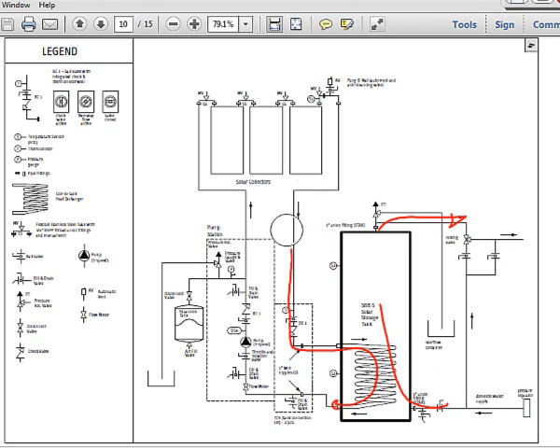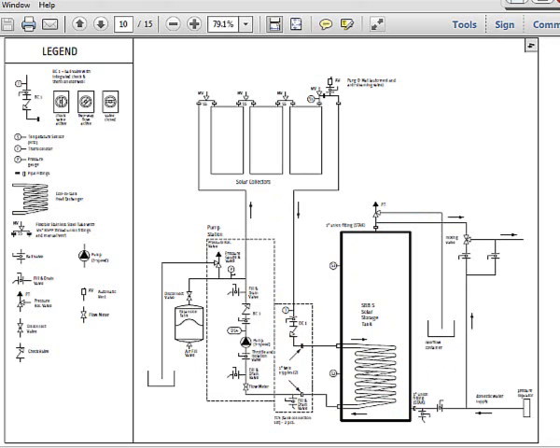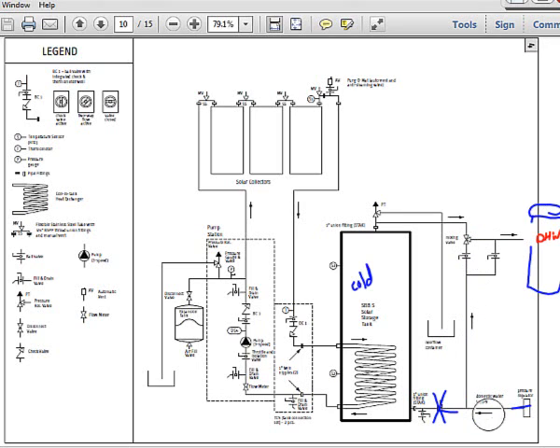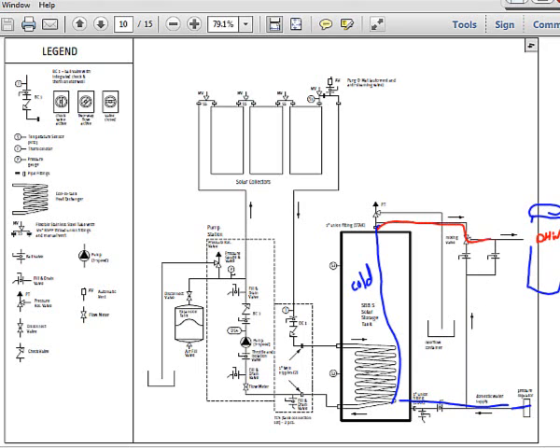A couple things to worry about in tank sizing and tank design and so forth. When we design fluids to flow, we always want to have ourselves ball valves predominantly in these systems because ball valves last longer. They have less inlet restrictions on them, so that will decrease the amount of pressure drops associated with each insertable item in it. And then the other fact is it gives me bypasses. Just a quick exclusion from the tank, but looking at how fluid flows. Here, the cold water comes in, I can turn this valve off right there, and I could force that domestic water supply to go this way and into, eventually, a storage tank. So I could have a secondary storage tank that, if this water got too cold, I could then have just a typical domestic hot water tank, a typical vertical tank right there that would provide heat. Or, when this is on, I can open that valve right there, the cold water comes in, cold water flows into this pressurized system, comes out, obviously, hot, through that mixing valve, and I'm providing hot water out to the system.